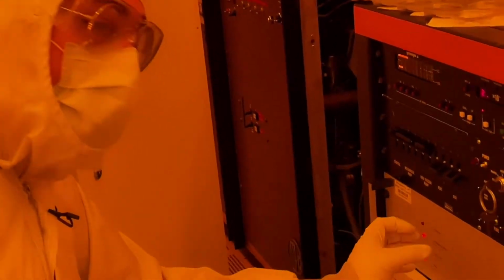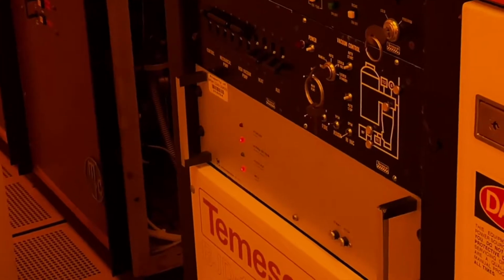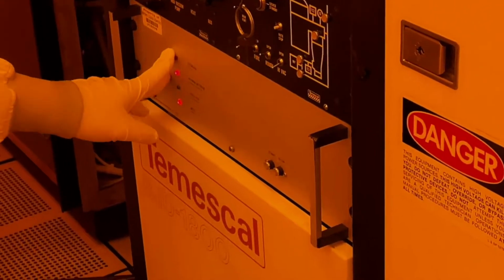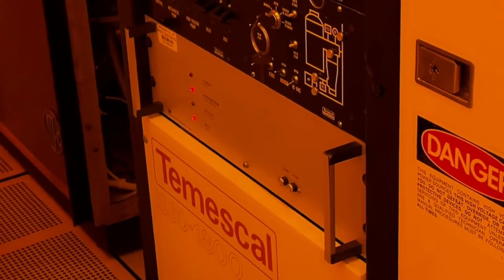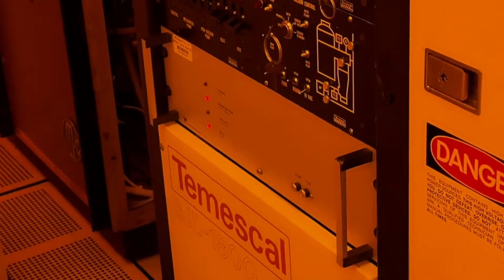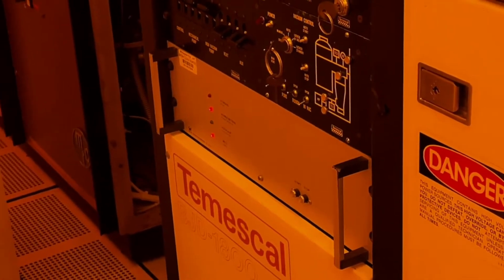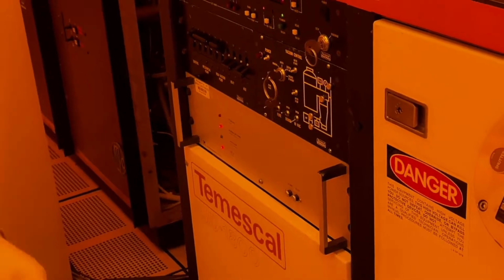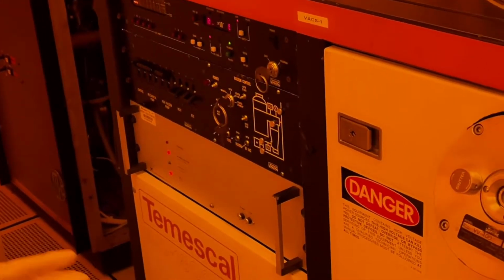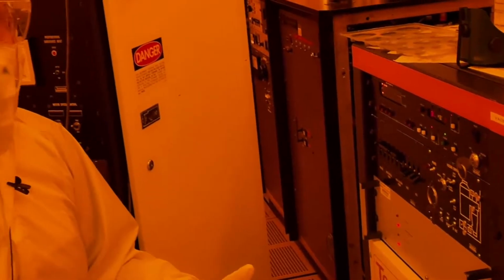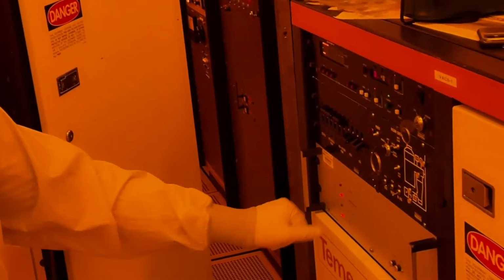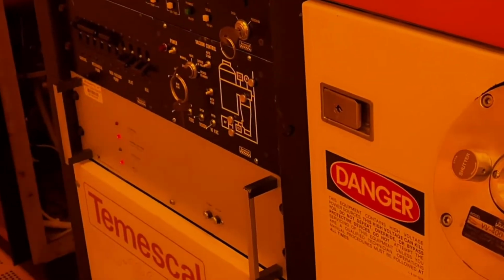Additionally, something that commonly happens when the power goes out is the turbo pump will go out. When this happens, it will go into an emergency operation where it utilizes battery power to spin the turbine down at a safe speed without damaging it, and then it will turn itself off. You may come in the next day and it's just not spinning. All you have to do is restart it.